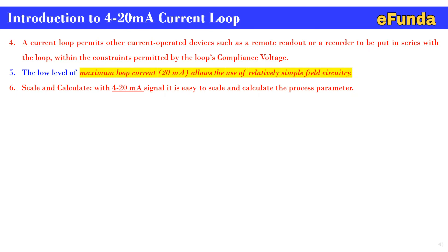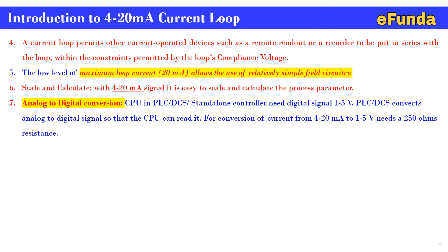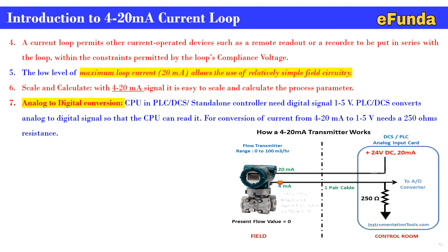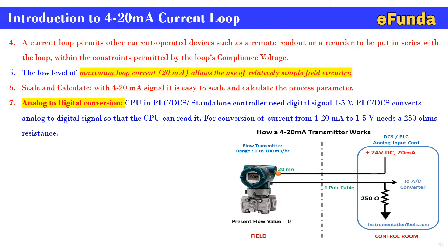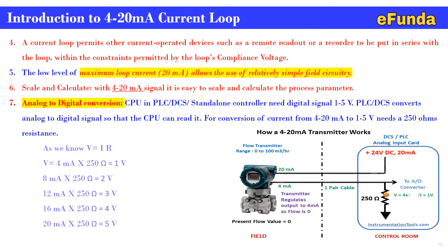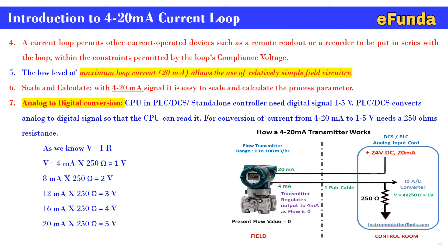Seventh, for analog to digital conversion, one can refer to the animation — a CPU can read the converted signal. To convert a current from 4 to 20 milliamp to 1 to 5 volt, a 250 ohm resistor is required. Using V = IR: 4 milliamp into 250 ohm equals 1 volt.